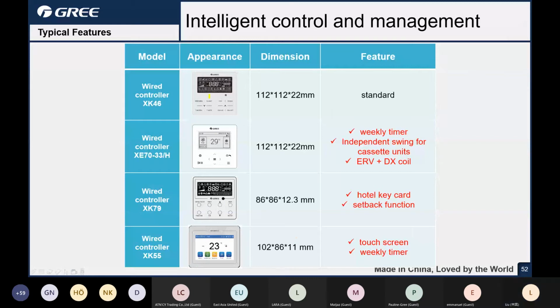And for the wired controller, XK46, it is the standard wired controller. And for this one, XE70, this one it has the weekly timer. And here, pay attention to this remark. It has the independent swing for cassette unit. You know, for GMV6, our new model of the cassette indoor unit, it can do the independent swing. The swing motor can be independently controlled. And if you want to realize the independent swing, you have to use the XE70, this controller. This is a special controller for the independent swing control.